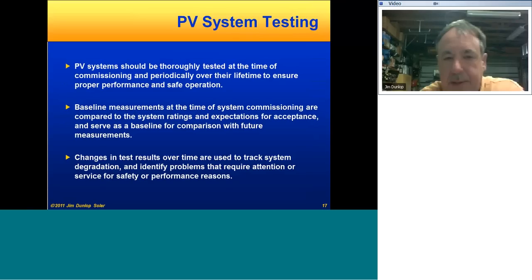So on testing, the main thing I'm going to get into is the type of test that would be done. I'm not going to talk too much about interpreting the results here or troubleshooting. Maybe that's for Thursday night, I guess, Richard. But any type of PV system needs to be tested, obviously, when it's commissioned and should be tested periodically over its lifetime. It's in addition to verifying performance from inverters and so forth.